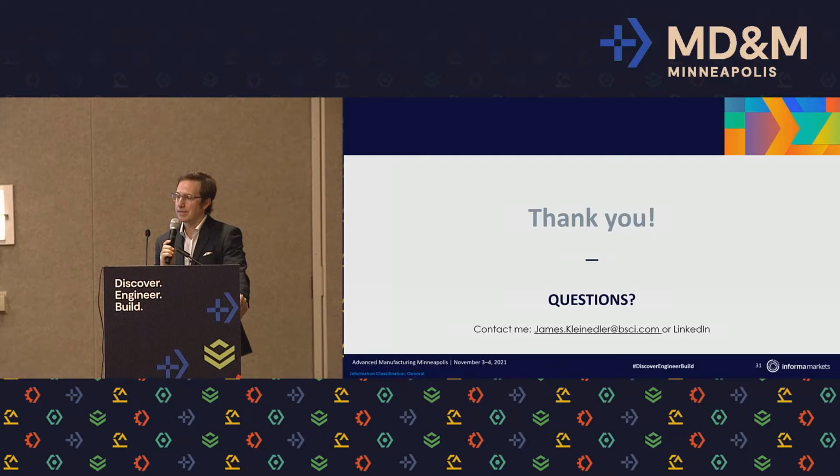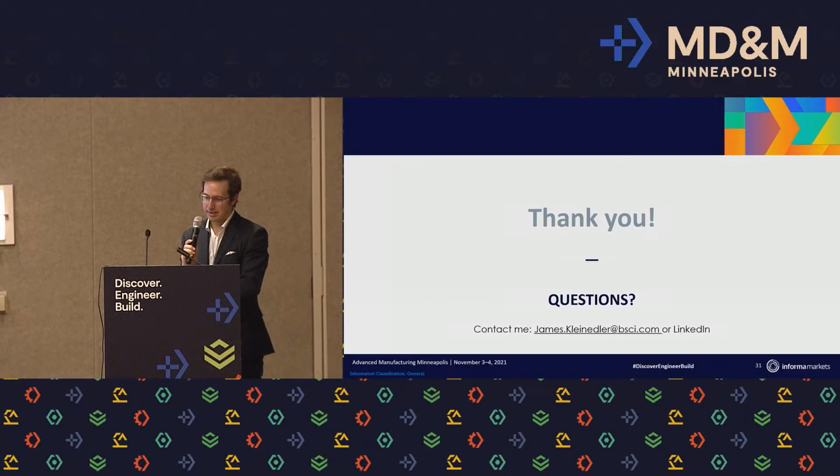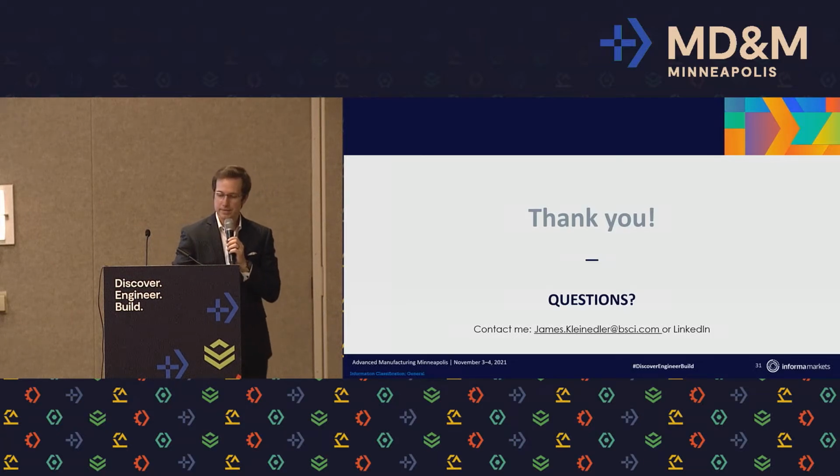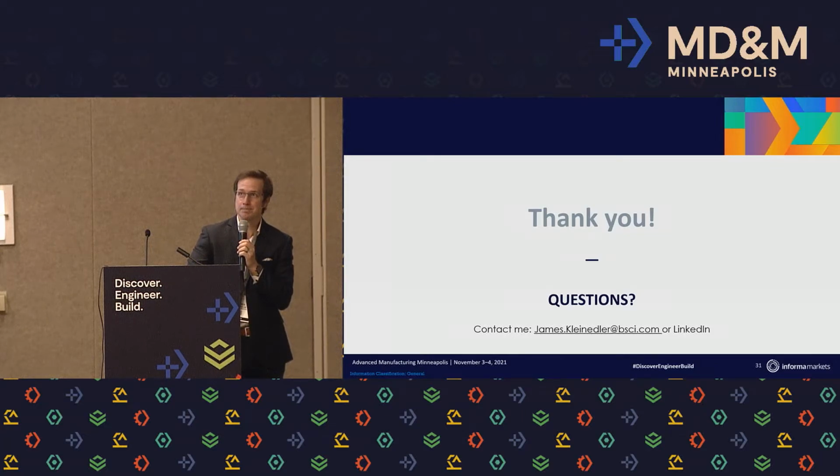The other thing you had a question about was OUS studies and how FDA views that. They're far more open to leveraging OUS data than they were years ago, 6, 7, 8 years ago. I think it's commonplace now for them to see in an application data from Australia or Western Europe or even Eastern Europe. So I don't see that as a showstopper. In the past, maybe it has been. If you have complaint data, OUS, I think the governing guidance would be FDA's guidance on foreign clinical data. If you just Google foreign clinical data and FDA guidance, it should pop up. But they have some expectations for what to do in that case.